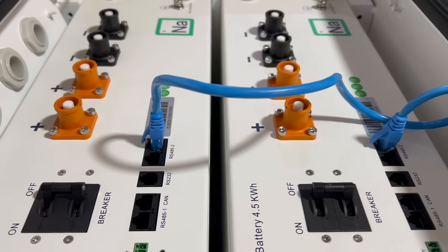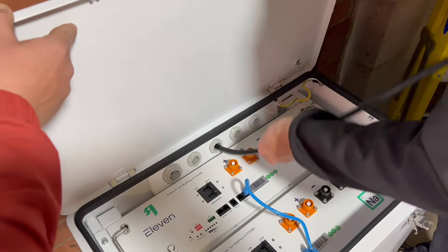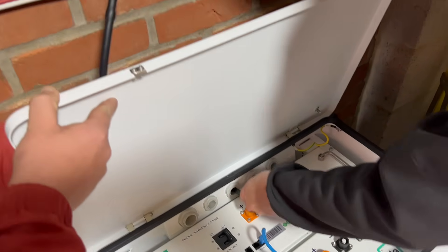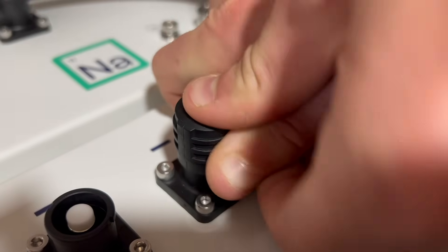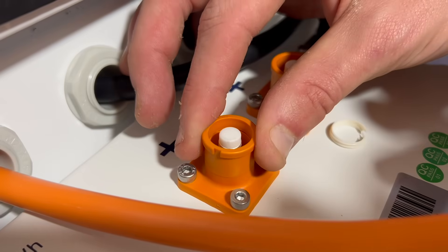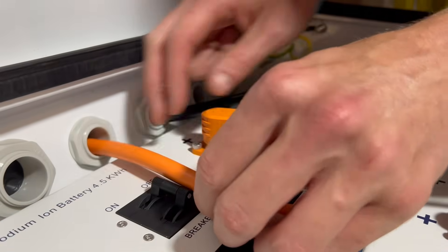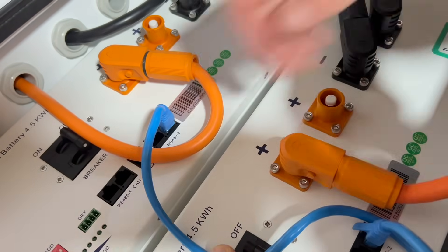This connection allows the inverter to talk to both batteries and control the flow of power to and from them. Then we start bringing in the beefy conductors — these are the DC cables that carry the current to and from the battery. They just thread through the stuffing glands and then they're a simple push-fit connection to the battery terminals. That's the external negative connection made, and now we'll do the same with the positive connection.